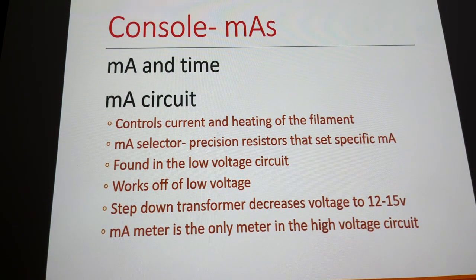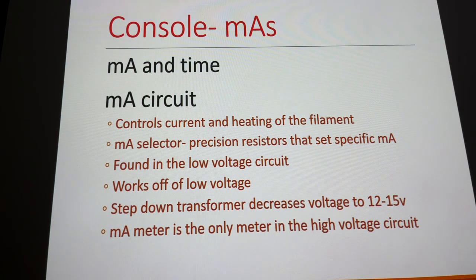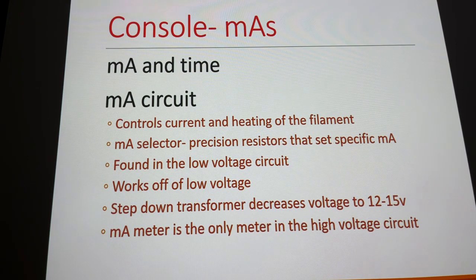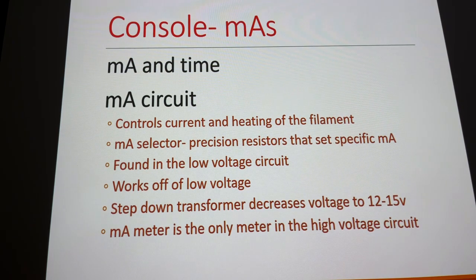What we have before exposure is MA. When you depress the prep button, you're only heating the filament. The more you heat the filament, the more electrons you collect in your space charge — your electron cloud — before sending them across the tube. MA is just heating of the filament to get it ready before we send electrons across to make X-rays. The MA selector is also a type of rheostat — it's your auto transformer for KVP, but MA selector is also a rheostat, increasing or decreasing current through precision resistors.